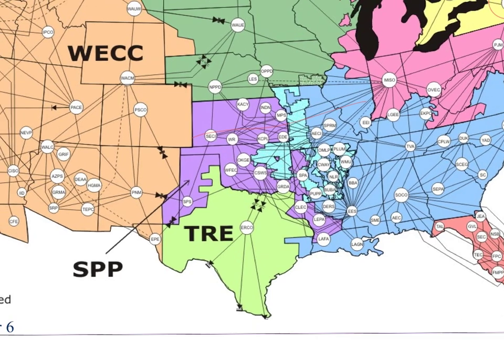Texas also, if you notice, it's got all those DC lines. So Texas is not part of FERC because all the interconnection from Texas to the rest of the U.S. is managed through DC lines. So they don't have FERC mandates because of the interstate commerce rules. The way the laws were written, they do not apply. So Texas does not fall under the mandate for FERC. So they are ERCOT and they've got their own rules, but they've decided to be separate.